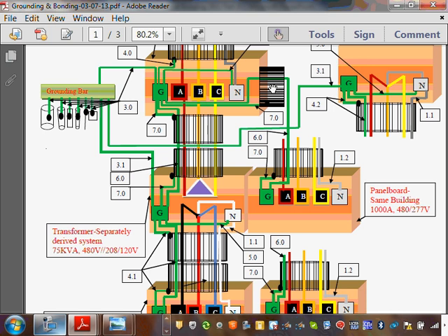Now, how? Yes, sir. Can you use that conduit as the equipment grounding conductor? Yes. Have that wire inside there? Yes. Now we're getting into the devil in the details. This is a 480/277 system. Bonding for a 480/277 system, if you don't have eccentric or concentric knockouts, very important, I always say the hole must match the conduit.